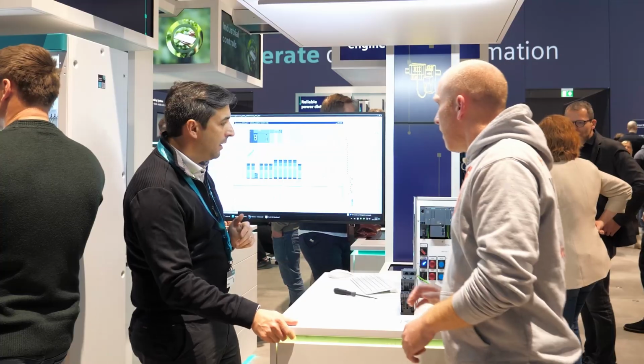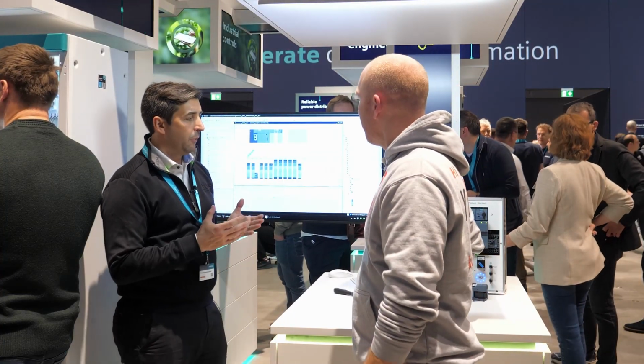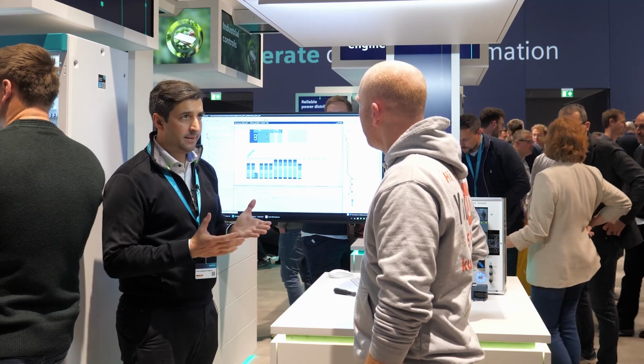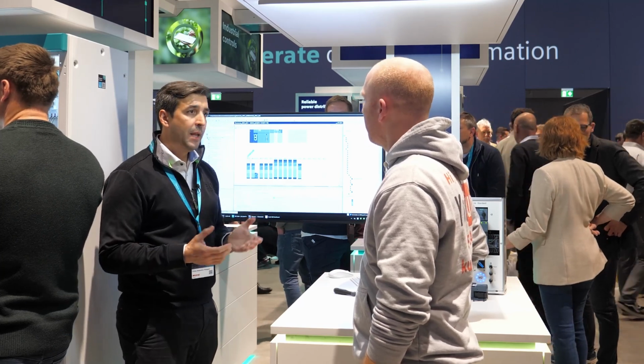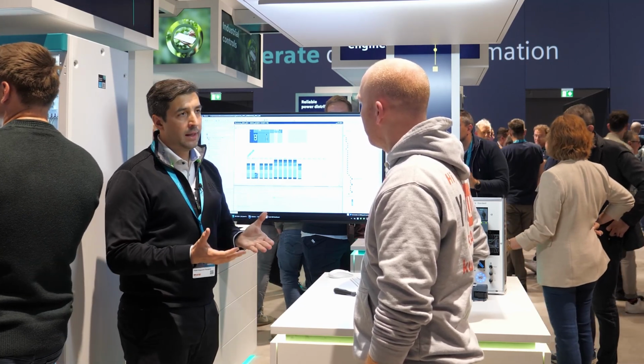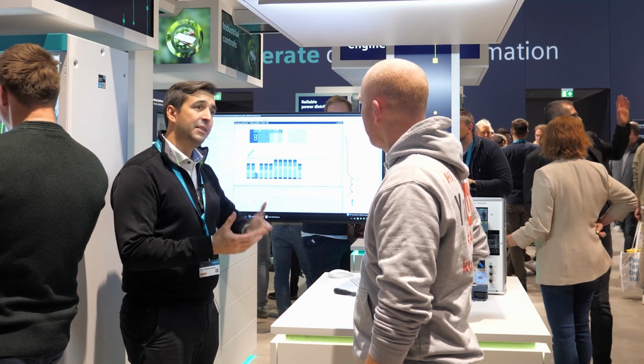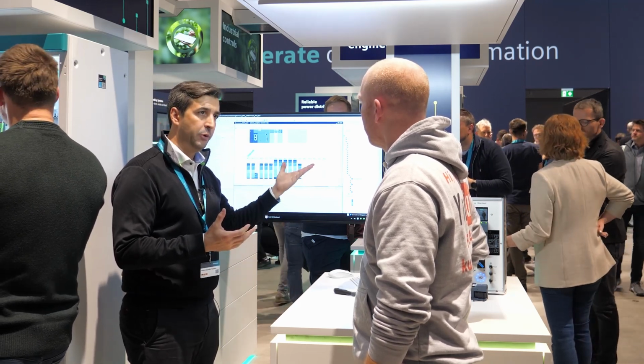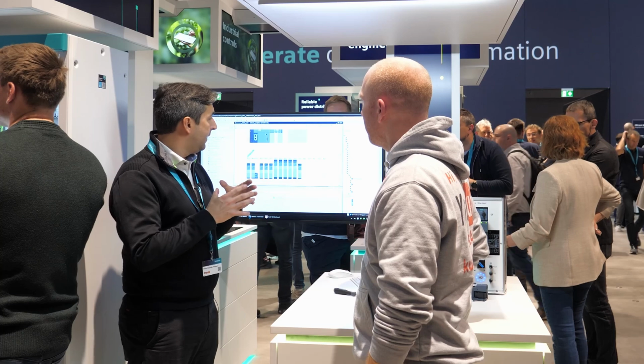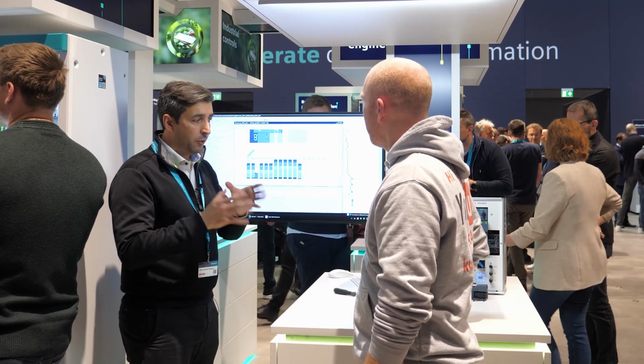Yeah, basically the advantage of this device is also that for the PLC it is like an input-output module. So the PLC sees this module like an input-output module, and all the diagnostics are automatically created on the PLC. And also all the behaviors of the input and output are here.